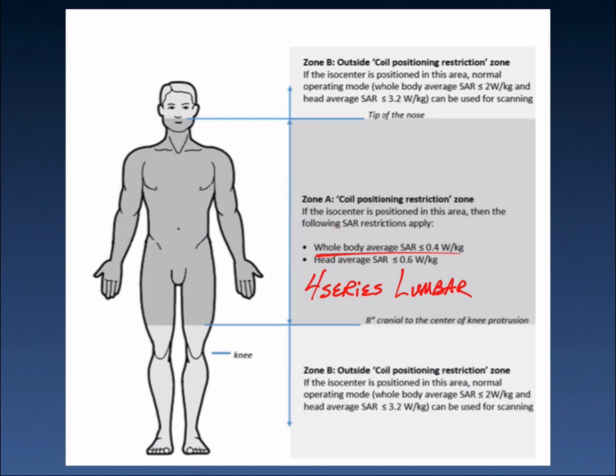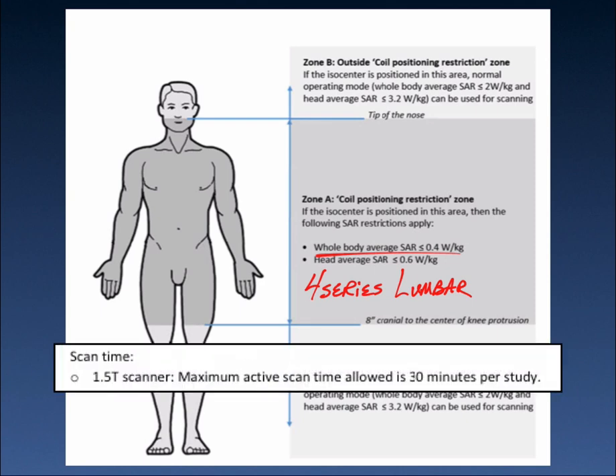We are going to acquire four series — well, five if you count the localizer — of lumbar spine exam. Additionally, one of the other conditions of use states that on a 1.5T system, the maximum active scan time, the total time of all the series, needs to be 30 minutes or less.